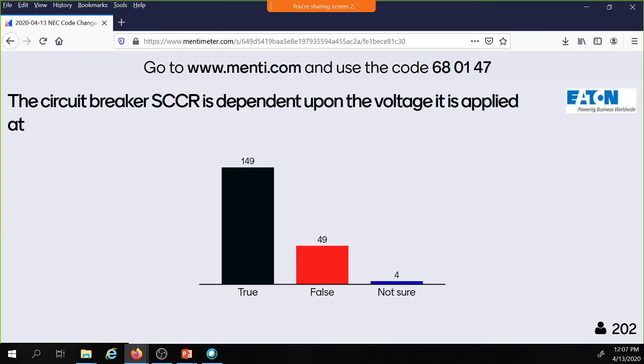All right. Circuit breakers have an interrupting rating. Fuses have an interrupting rating. We're going to talk a little bit more about that in this program, but I know I covered it in my fault current class not last Monday. Geez, that would be two Mondays ago, two weeks ago.